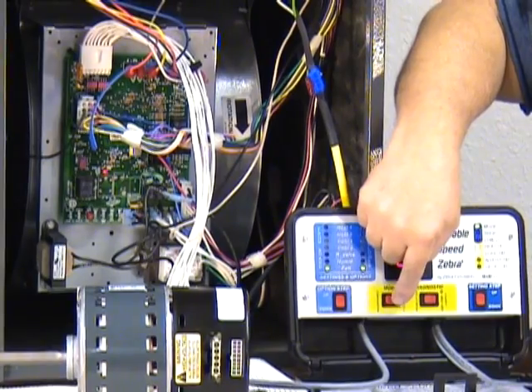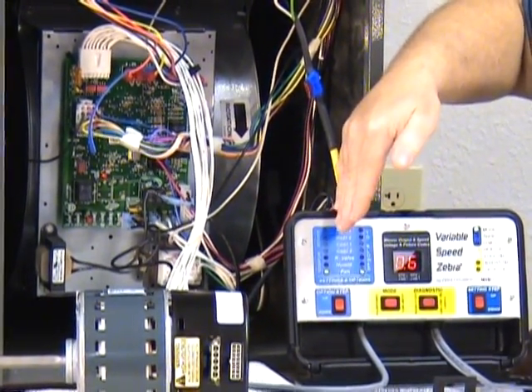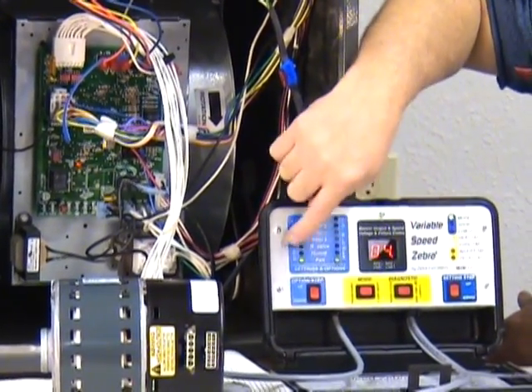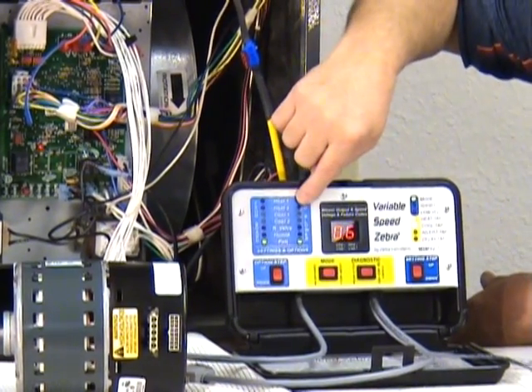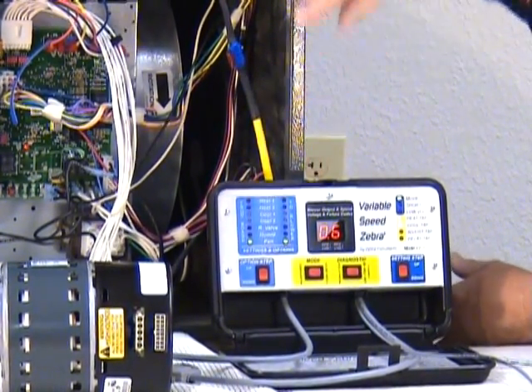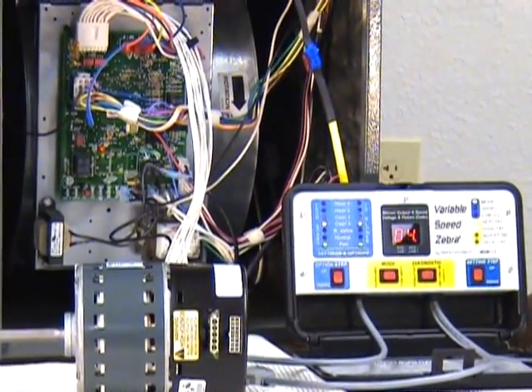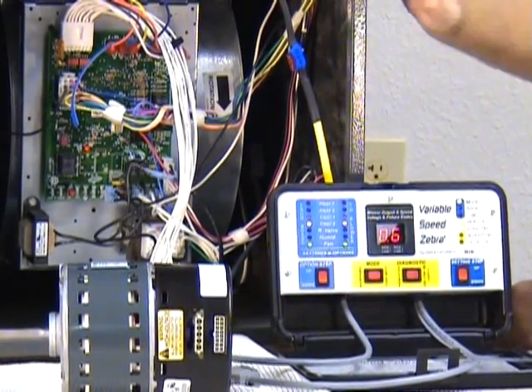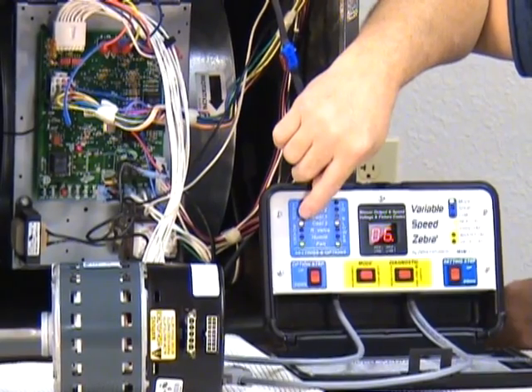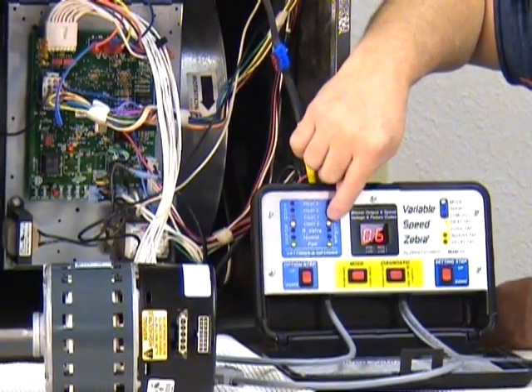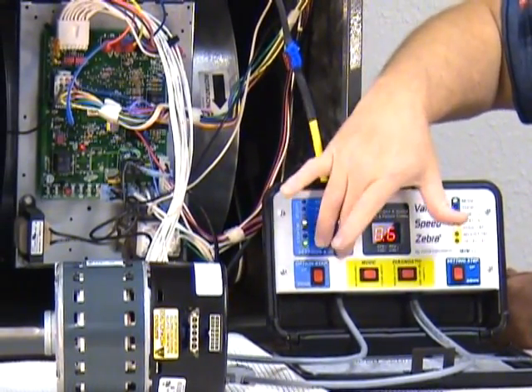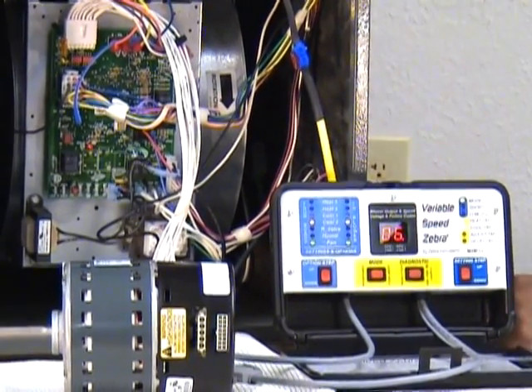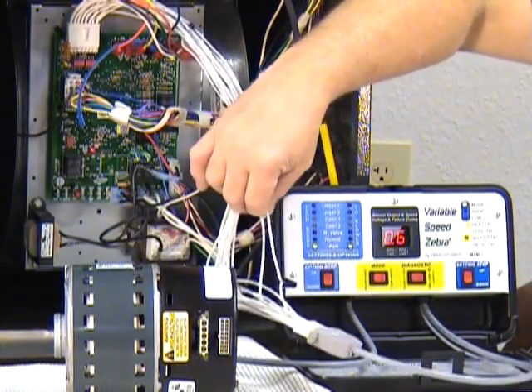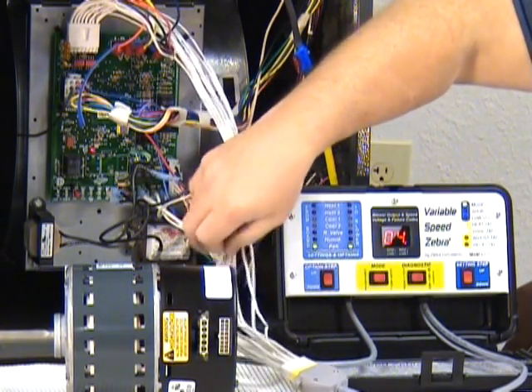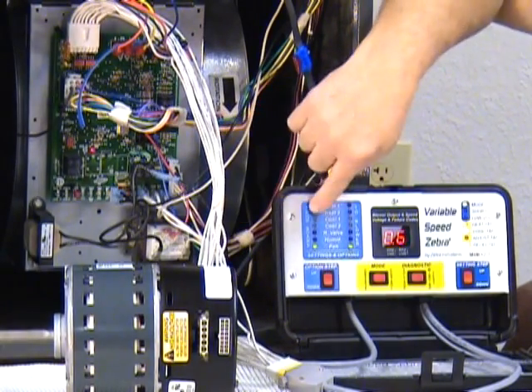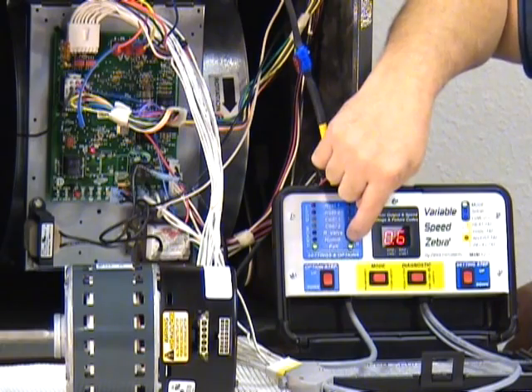If you throw this mode switch into control position, it will split this section. Right now, in the observe mode, any signal that lights up on this side will be passed along to this side. If we turn the cool speed on, we notice our air handler speeds up a bit, and the cool light comes on this side, and it's passed along to this side too. All we're doing is observing. So all these lights on one side will always be the same on the other side in observation mode. Those lights are just like seeing the electricity flowing in that wire. If that particular wire happens to be the signal line for the fan, you're seeing it's coming in from the board green and going out green to the motor connector.